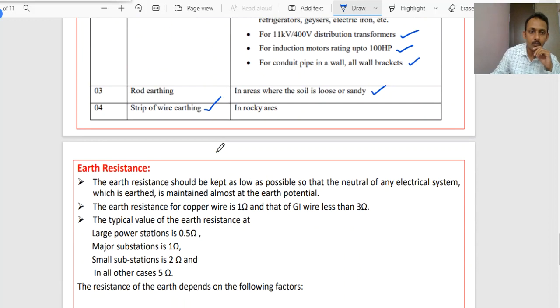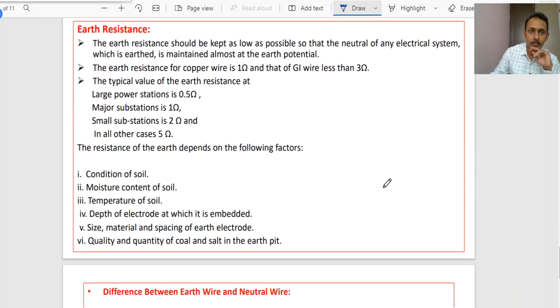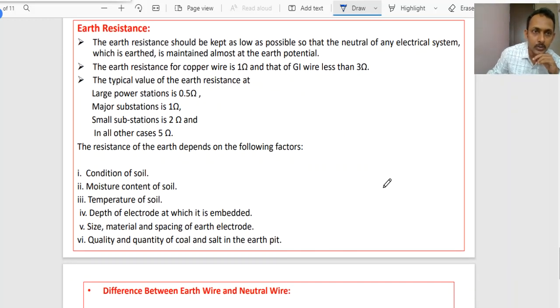Now coming to the earth resistance, the resistance offered by the earth wire should be as low as possible, so that the neutral of any electrical system which is earthed will be maintained almost at the earth potential. This is very, very important. Now how much should be the value of earth resistance? How much should be the minimum value to be maintained?